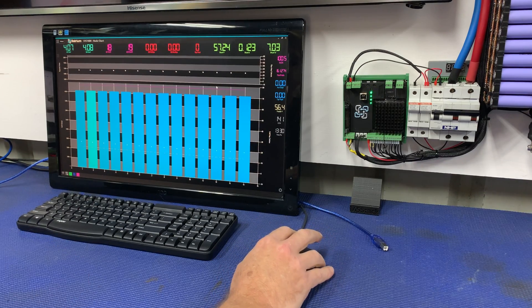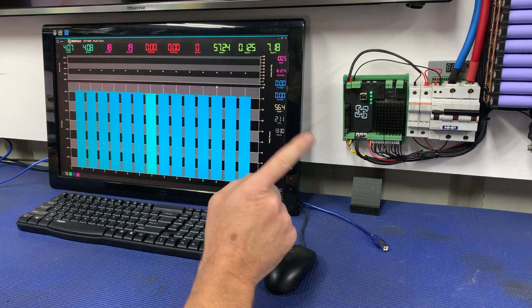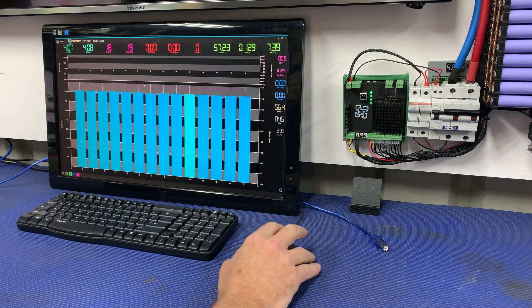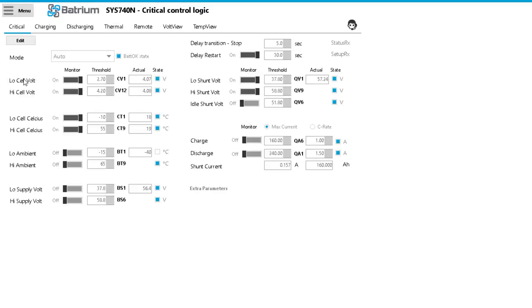The last thing I've got to do is configure the shunt trip to operate correctly and the parameters we'll be using for that is under control logic and under critical. So we've got low cell volt, high cell volt is both turned on.